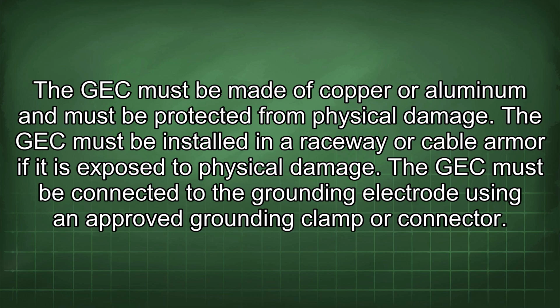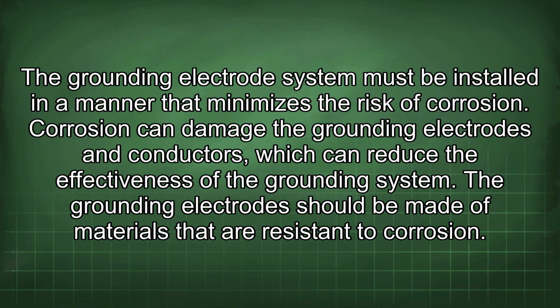The GEC must be installed in a raceway or cable armor if it is exposed to physical damage. The GEC must be connected to the grounding electrode using an approved grounding clamp or connector. The grounding electrode system must be installed in a manner that minimizes the risk of corrosion. Corrosion can damage the grounding electrodes and conductors, which can reduce the effectiveness of the grounding system.